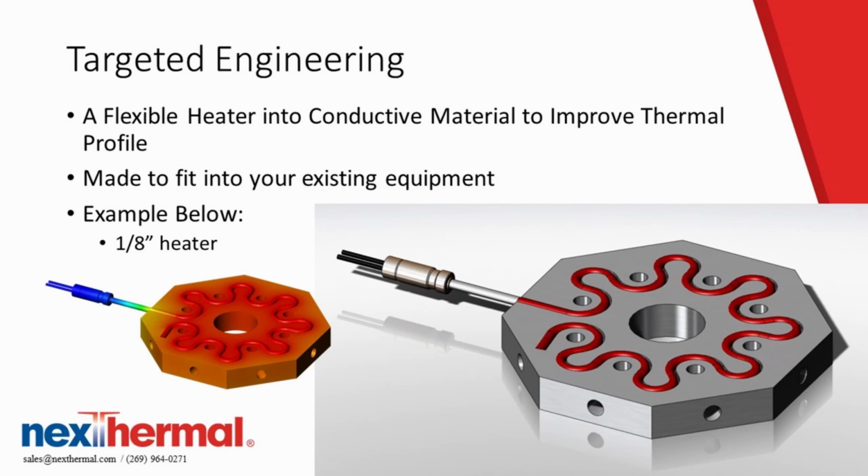Here are some of our flexible heaters and conductive material to improve the thermal profile. The minimum bending radius is 6 millimeters. It's flexible, hand formable, and can be sealed for washdown applications. It's ideal for low mass, small footprint applications. Those are about the size of a hockey puck. We can incorporate a Type J thermocouple, positioned pretty much anywhere in that coil heater. Usually it's at the tip or the center.